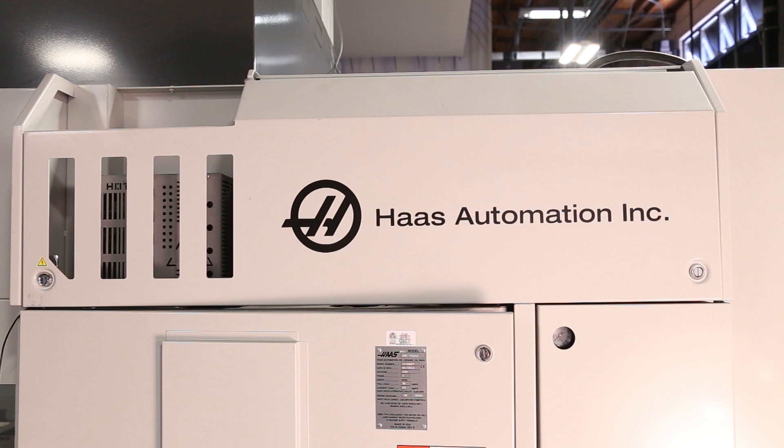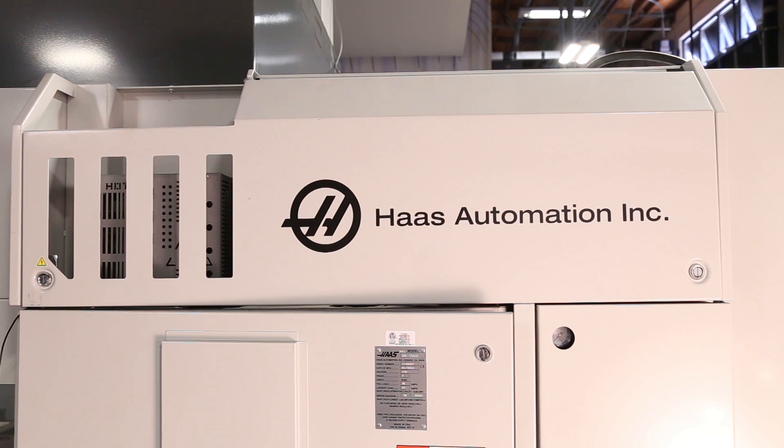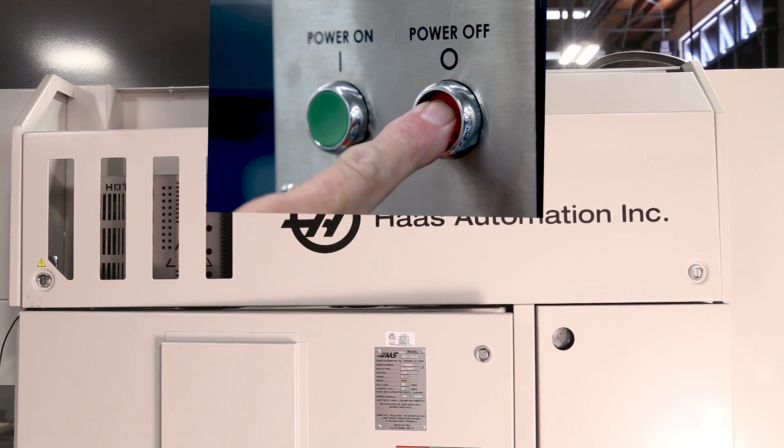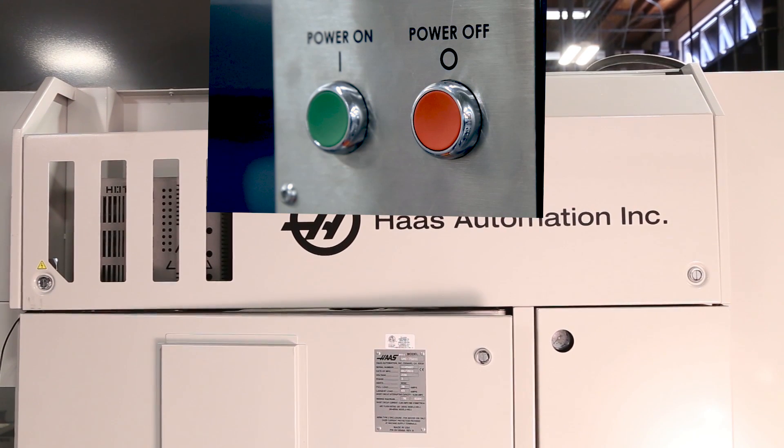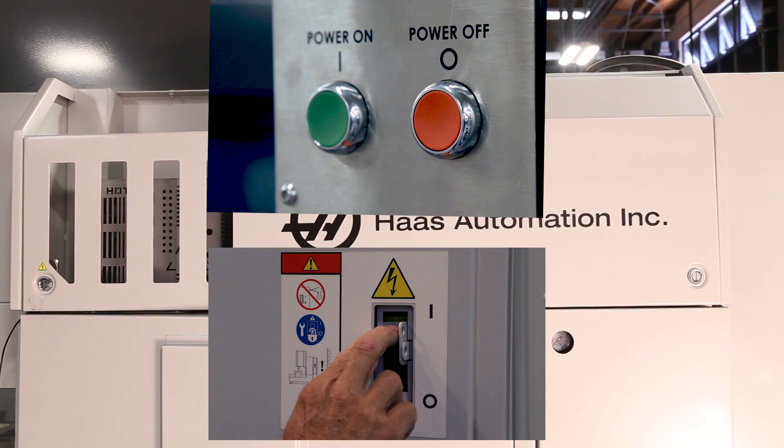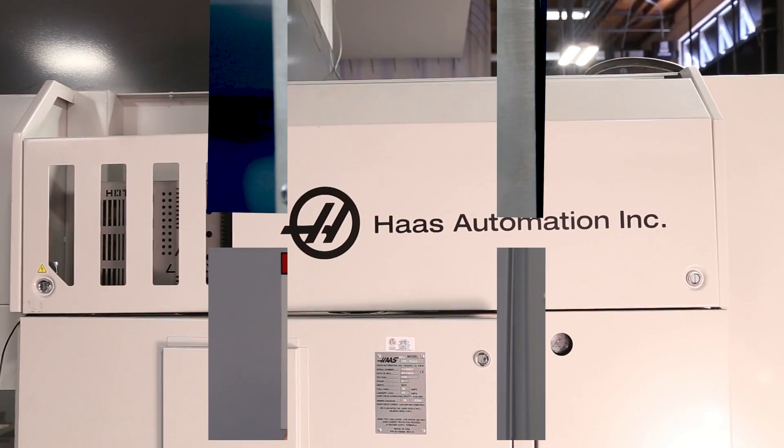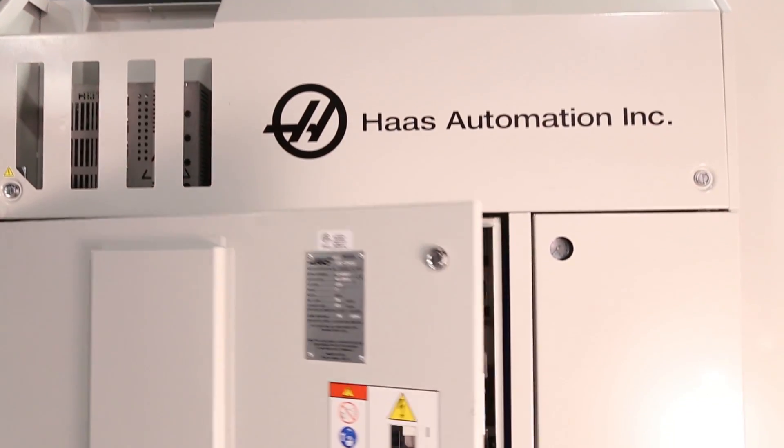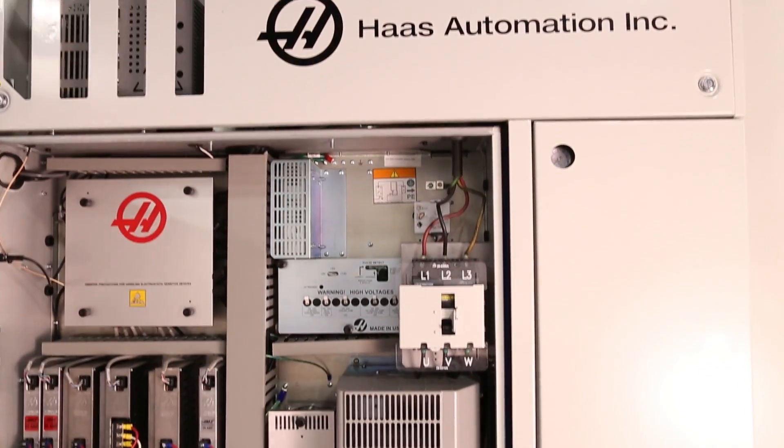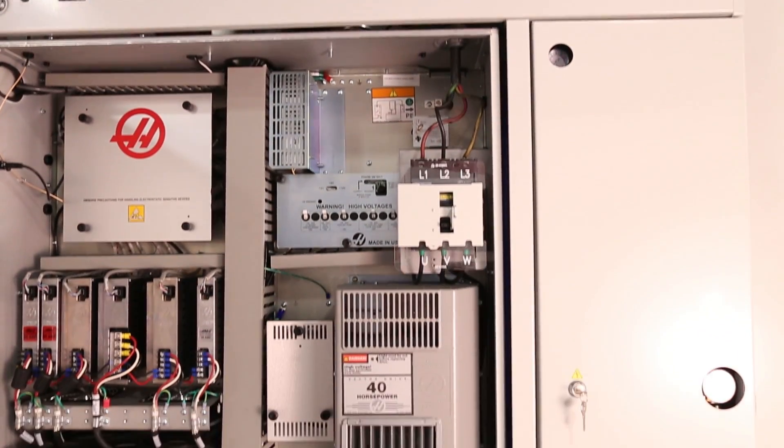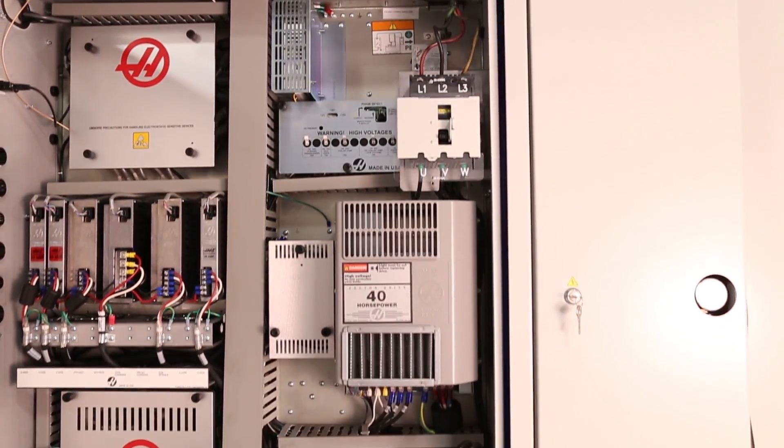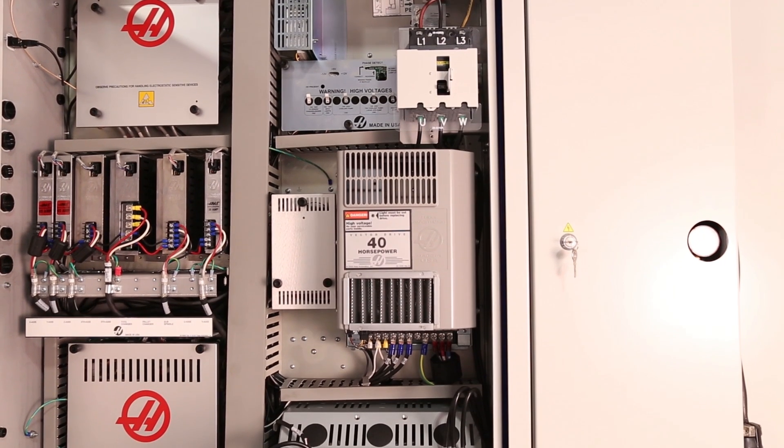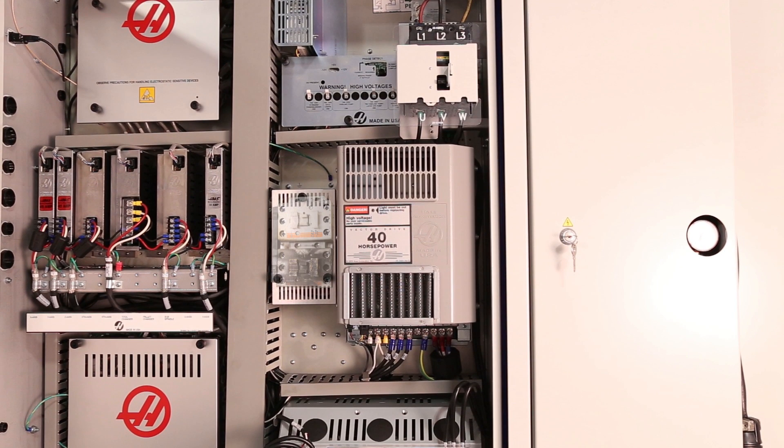Here's the easiest way to see if the Y-delta has failed. Power down the machine, set the main circuit breaker to the off position, open the control cabinet, and smell the air. If it smells burnt, the contactor is the likely cause.